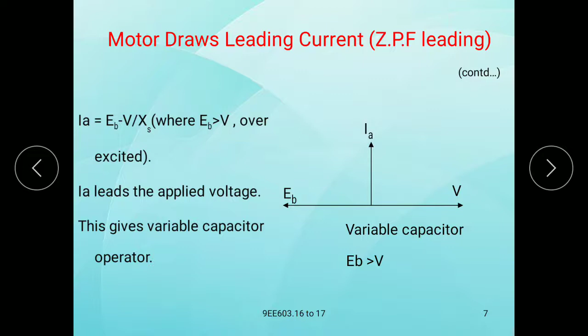So for the variable capacitor, the condition is over excitation. Over excitation means the EB value is greater than V. Now the armature current IA is equal to (EB minus V) by XS. The condition is over excitation, that means EB is greater than V. So IA leads the applied voltage. Why? It is acting as a capacitor. So this gives variable capacitor operation.